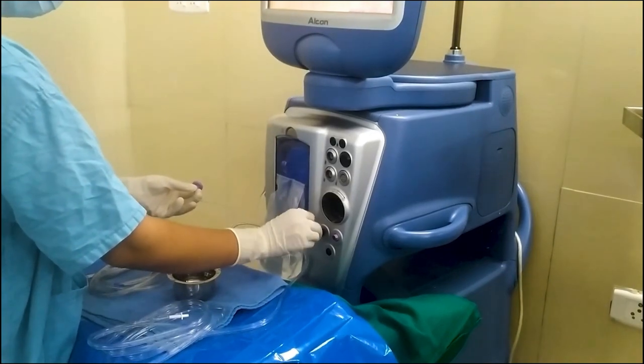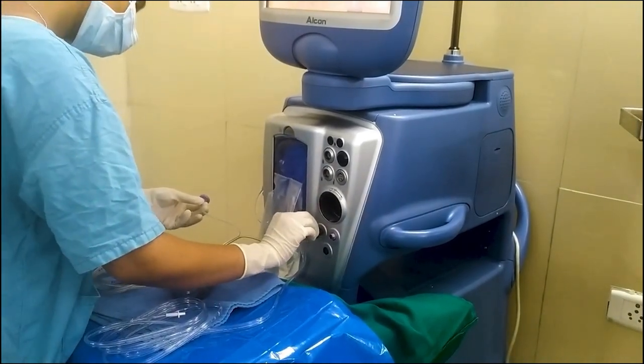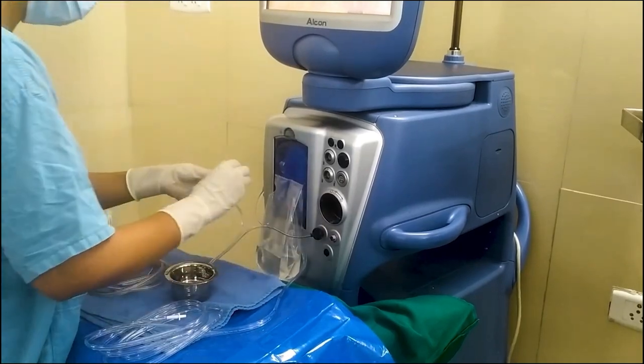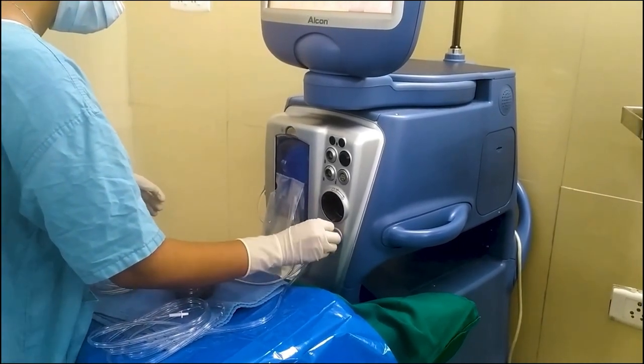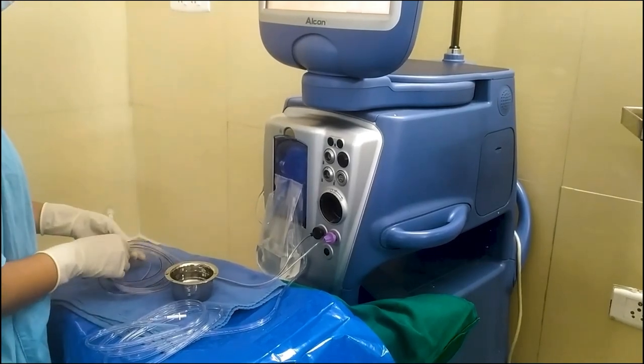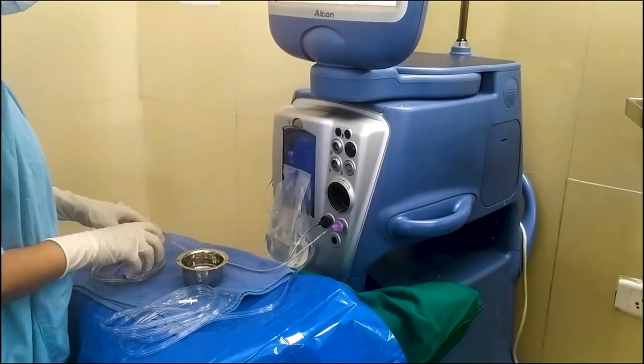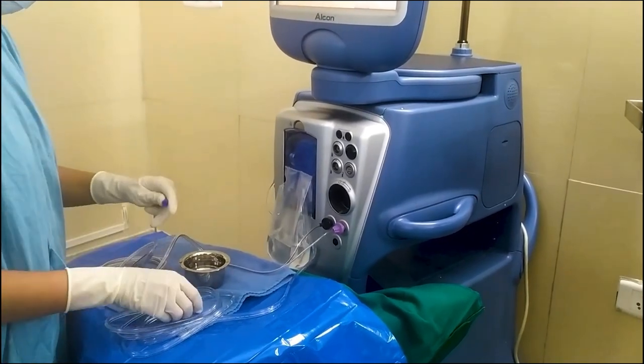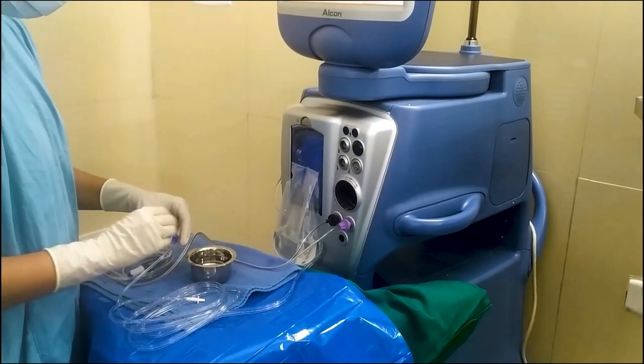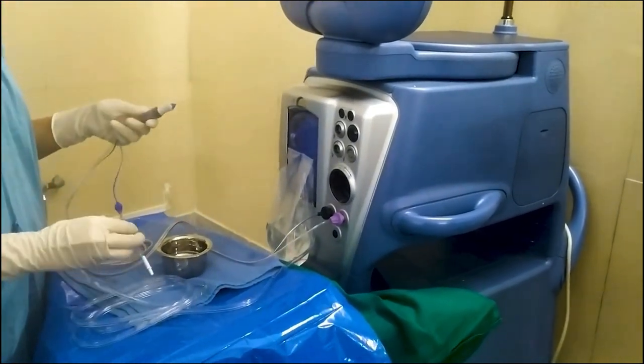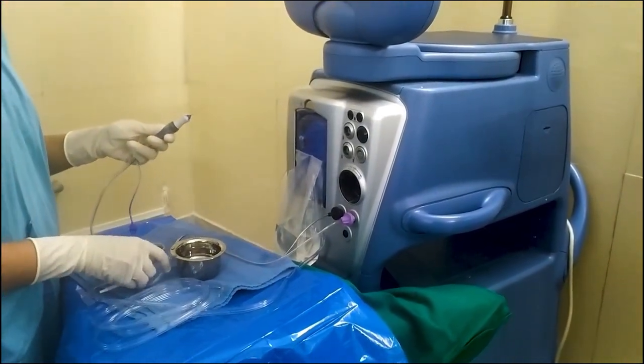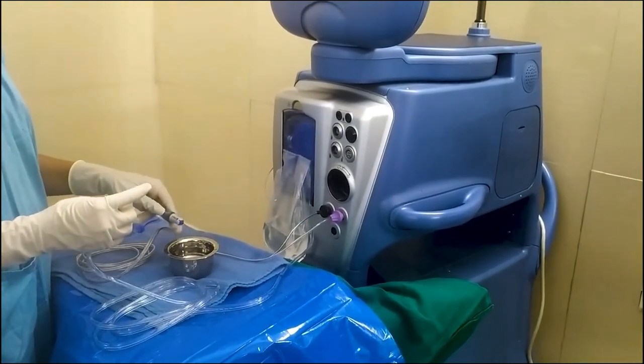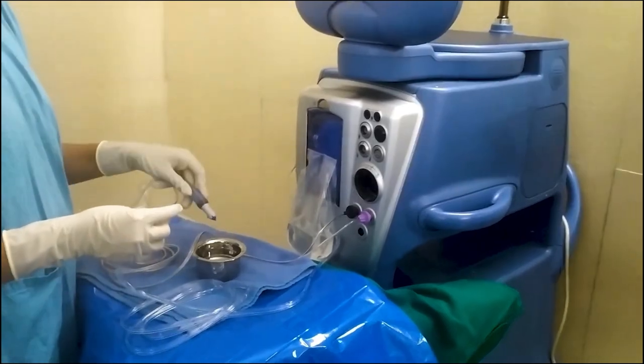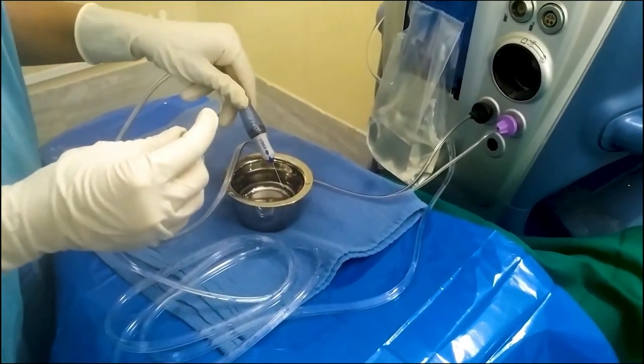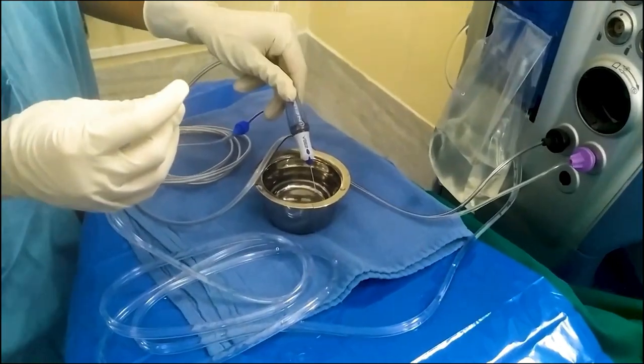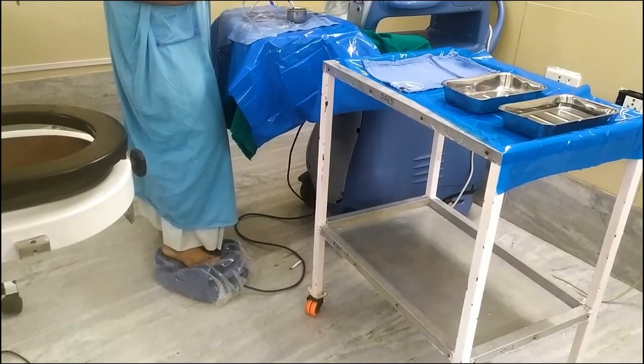So now here we can see that there is a bowl in which we have to clean the vitrectomy probe. Clean it till the bowl is empty. After attaching it to the phaco machine, the cutter is then taken and it is cleaned using the RO filter water in the bowl. Also the foot pedal is pressed during that process.